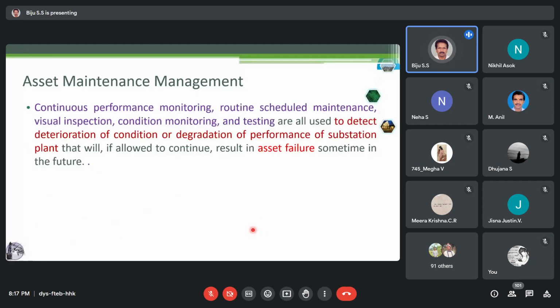Continuous performance monitoring, routine scheduled maintenance, visual inspection, condition monitoring, and testing are all used to detect deterioration of the condition or degradation of performance of substation plant. That will, if allowed to continue, result in asset failure sometime in the near future. This is a technique.